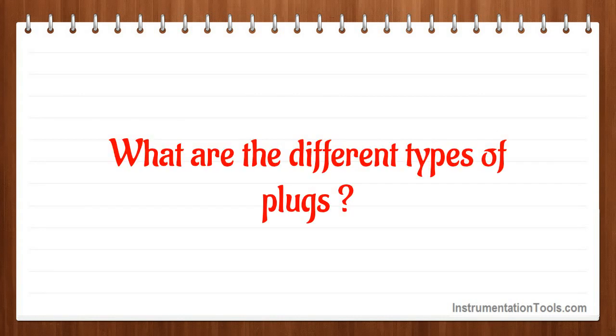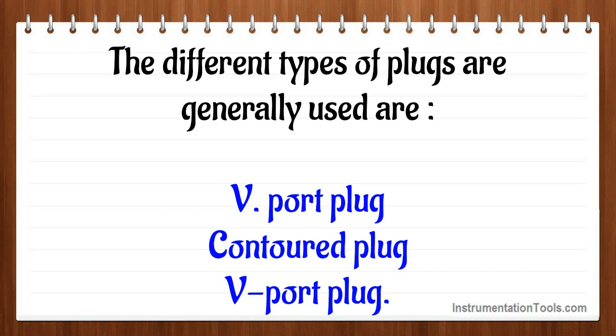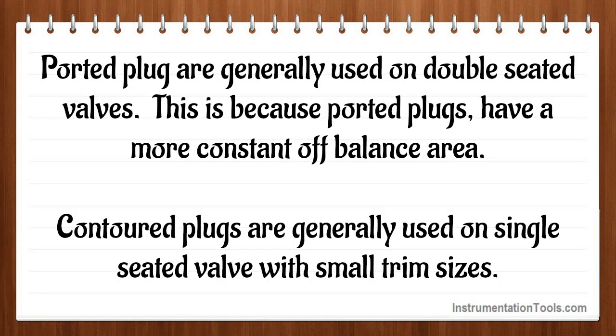What are the different types of plugs? The different types of plugs generally used are v-port plug and contoured plug. Ported plugs are generally used on double seated valves because ported plugs have a more constant off-balance area. Contoured plugs are generally used on single seated valves with small trim sizes.